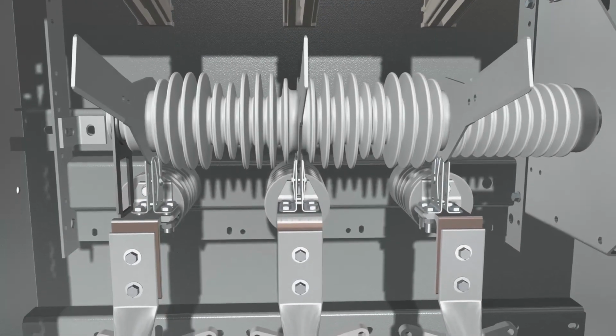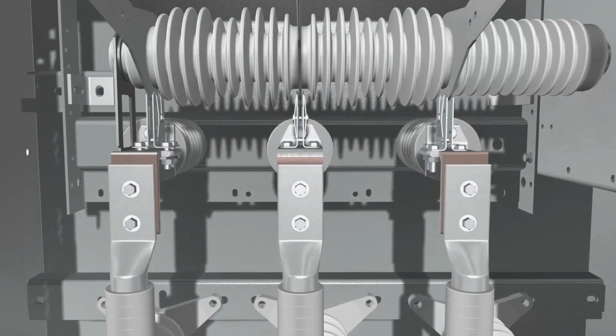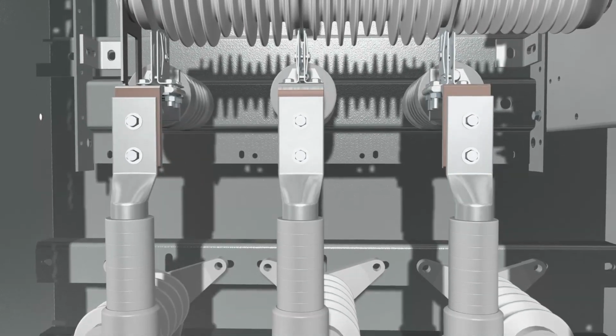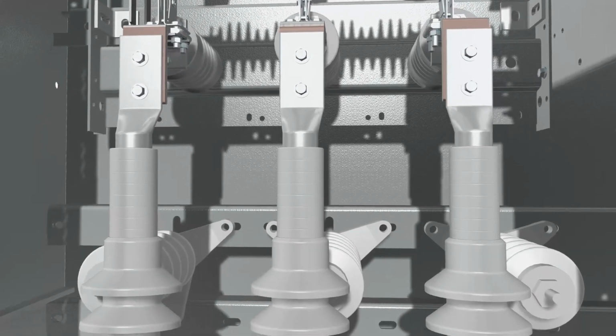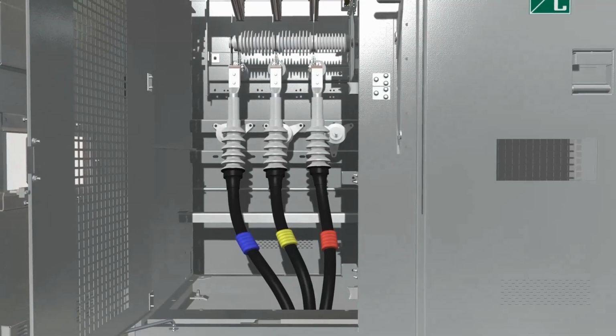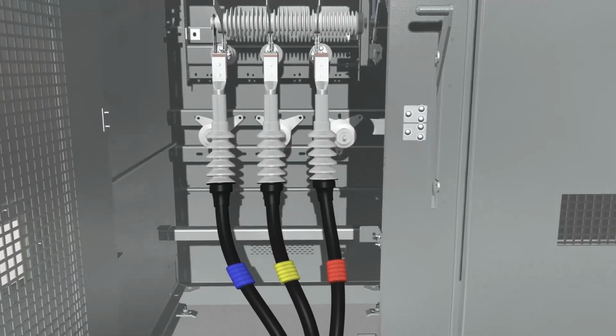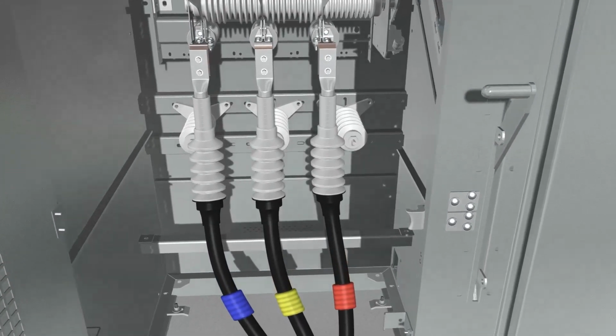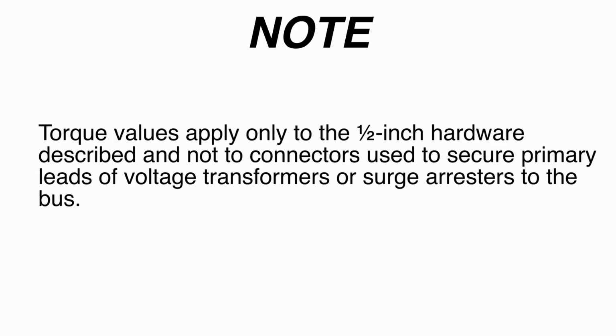S&C's custom metal-enclosed switchgear can be provided with different material combinations of bus terminal pads and connectors. See page 21 of the written instructions for specific details regarding these steps. Note: torque values apply only to the 1/2 inch hardware described and not to connectors used to secure primary leads of voltage transformers or surge arresters to the bus.